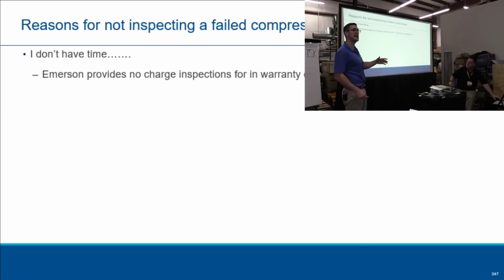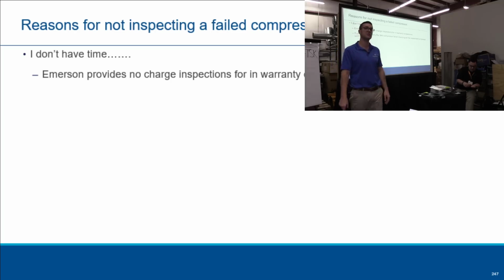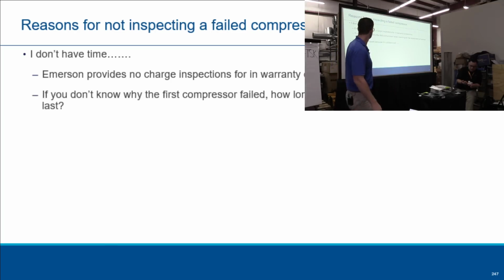Like Don said, if it's in that warranty period, you go back to your distributor and say, I need an inspection. I don't know why it failed. We want to help you figure that out. Okay? If you don't know why the first compressor failed, how long will it take until the second one fails? The compressor failed because it's old or worn out. It's not true. Maybe less efficient, but it didn't fail because it's old or worn out. A properly selected, applied and maintained compressor has a design life of 15 years.